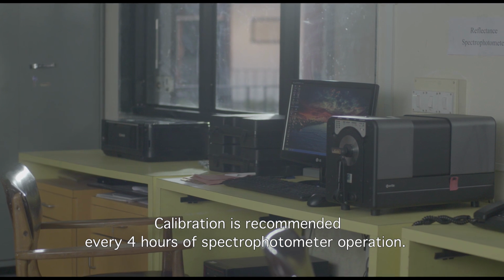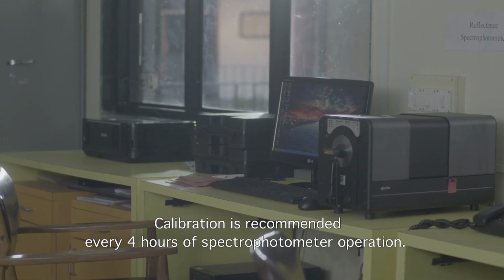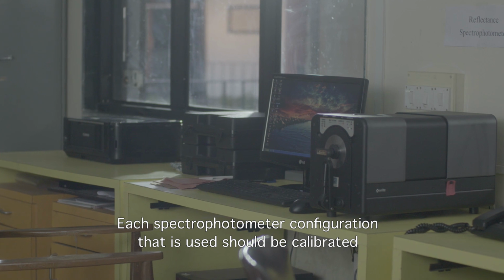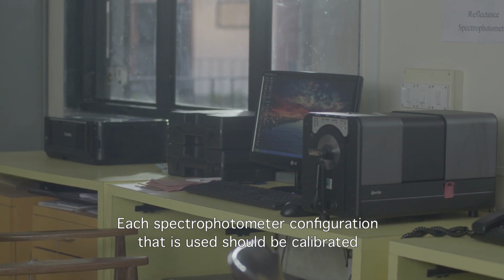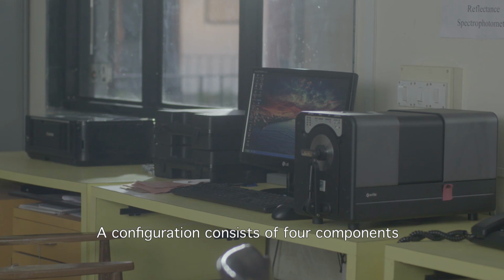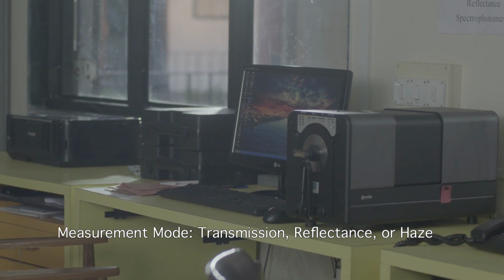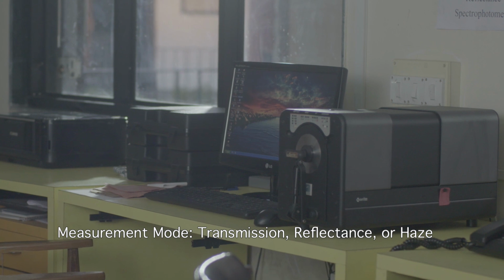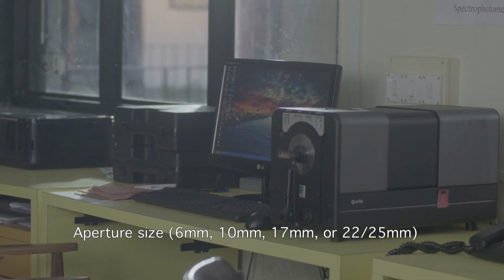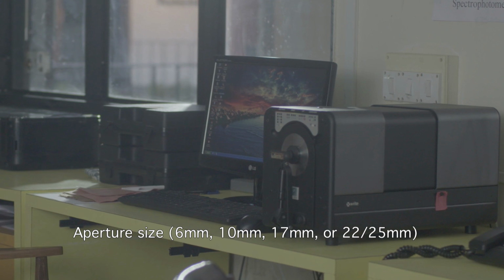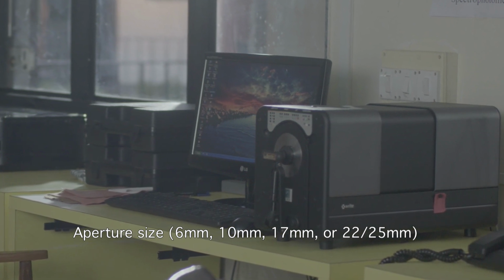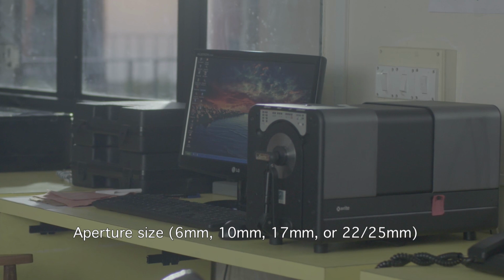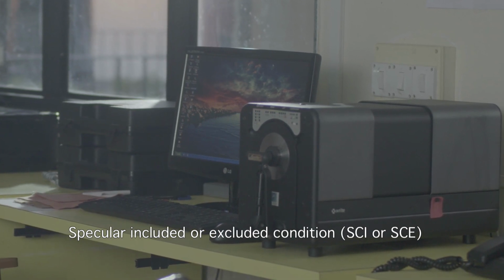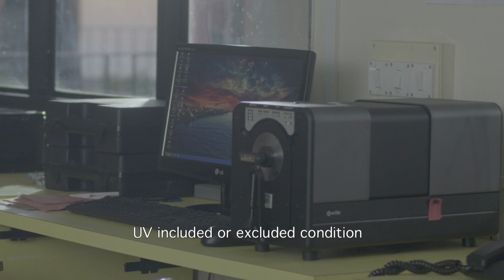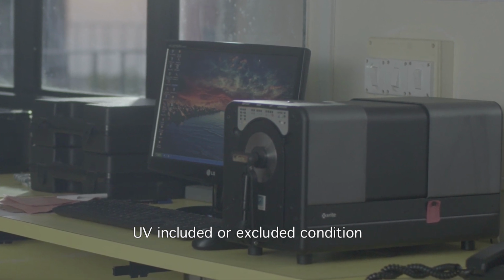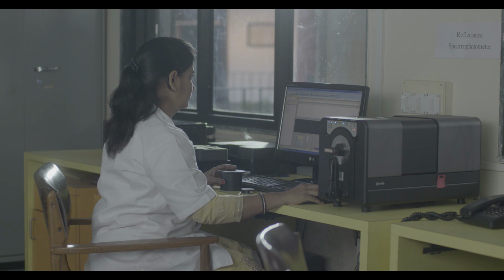Calibration is recommended every 4 hours of spectrophotometer operation. Each spectrophotometer configuration that is used should be calibrated. A configuration consists of 4 components: measurement mode, that is transmission, reflectance or haze; aperture size 6 mm, 10 mm, 17 mm or 22 or 25 mm; specular included or excluded conditions; UV included or excluded conditions. Check all configuration of calibration.